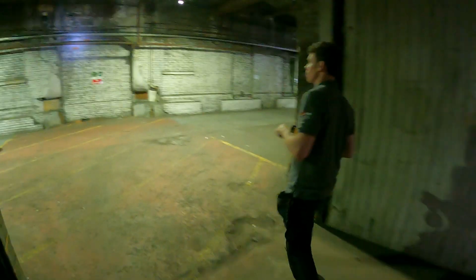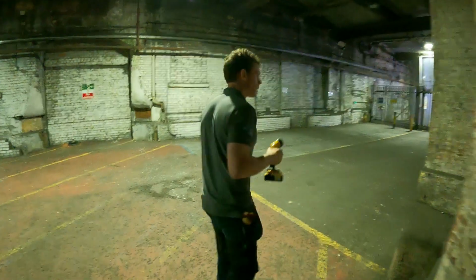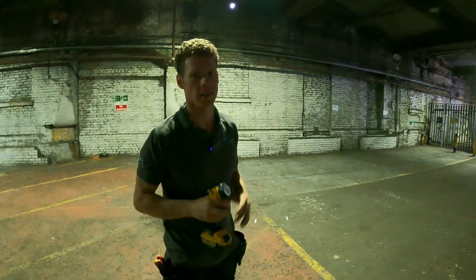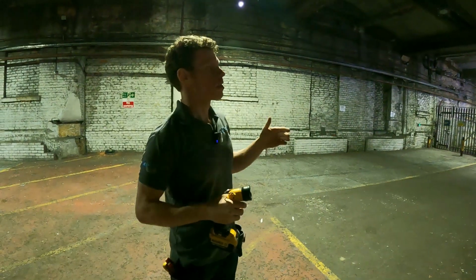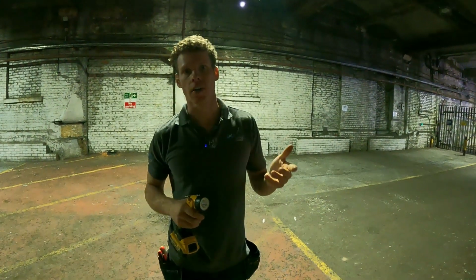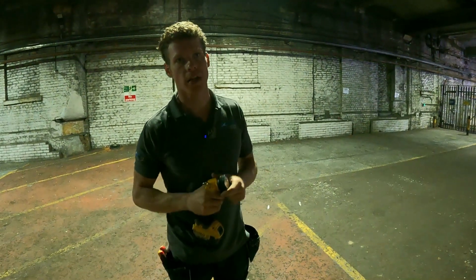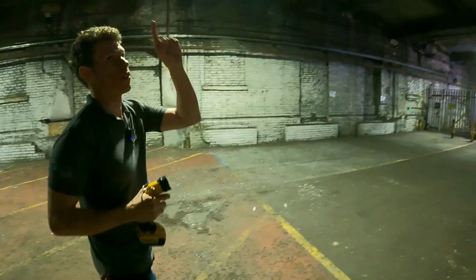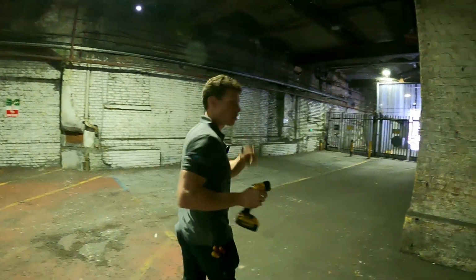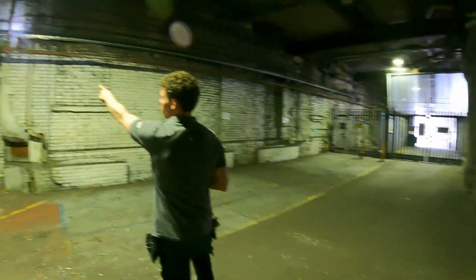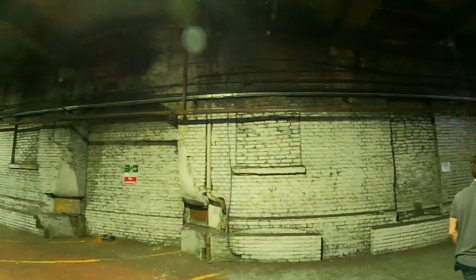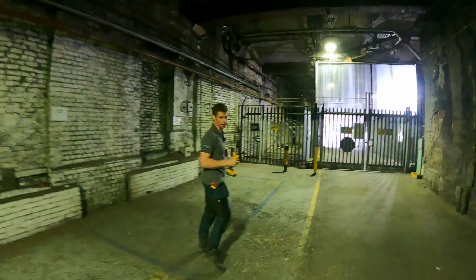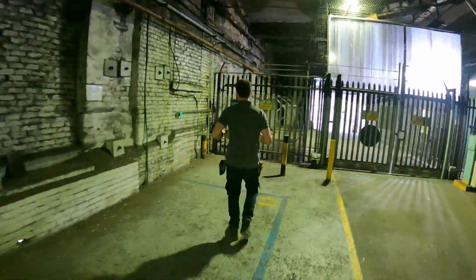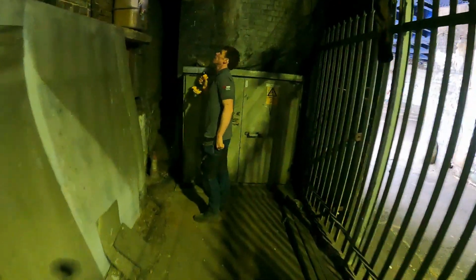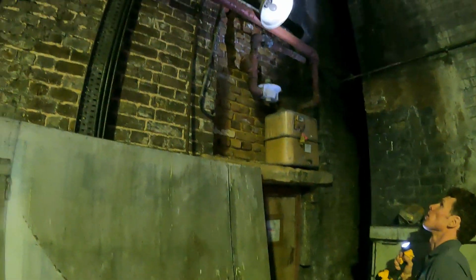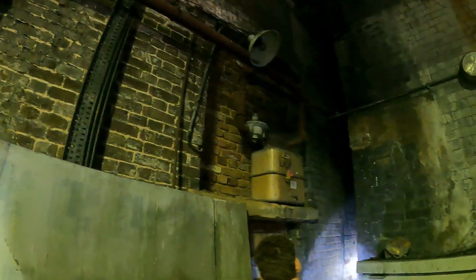The other thing I'd like to do as part of the visual is find all of the main bonding conductors to all the extraneous conductive parts entering the building. The water mains coming into the building is plastic, so the other extraneous conductive part entering from outside is going to be the gas. There's no bonding where the gas pipe enters these arches, nor where it splits over at that stopcock. So let's go over to the gas meter and see if we've got any bonding there. Okay, that's the main gas meter, and there's no bonding to that at all.